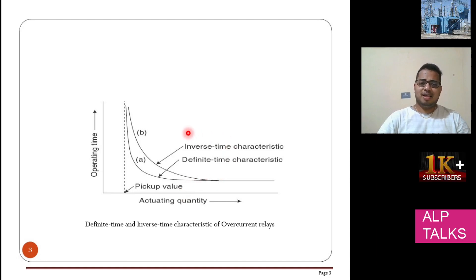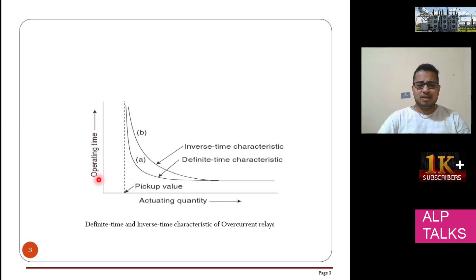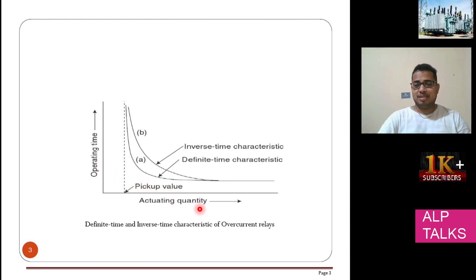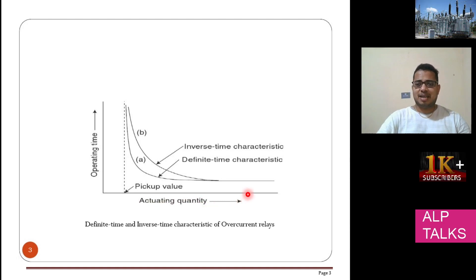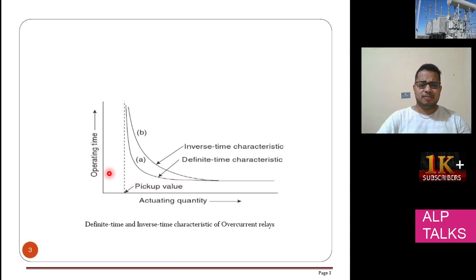This characteristic is very important. On the x-axis you have the actuating quantity, and on the y-axis you have the operating time. The actuating quantity is the current value — for example, if instead of 100 amps, 200, 300, or 400 amps is coming, it needs to be disconnected very quickly, otherwise some problem will happen. So within very less time the relay will operate. If the current amplitude is very less, then no problem — it can withstand for more time. So here you have definite time characteristics and inverse time characteristics.